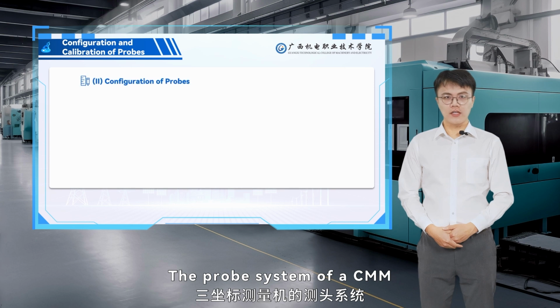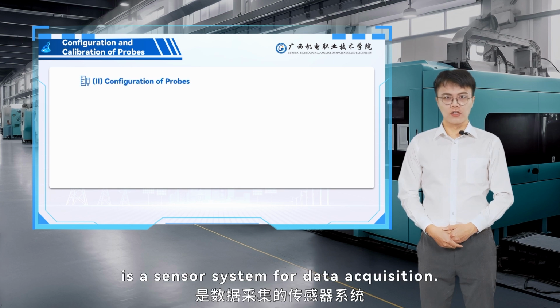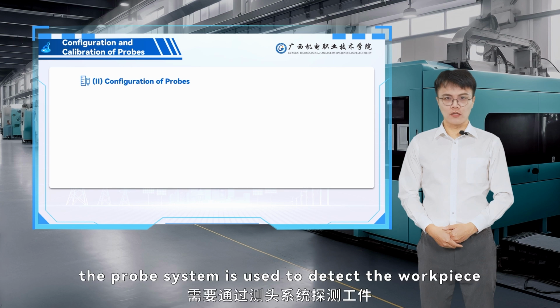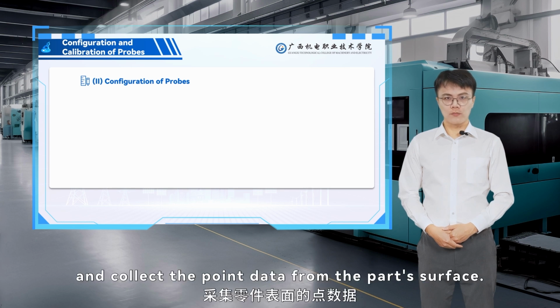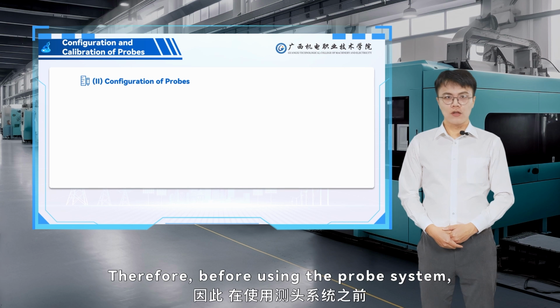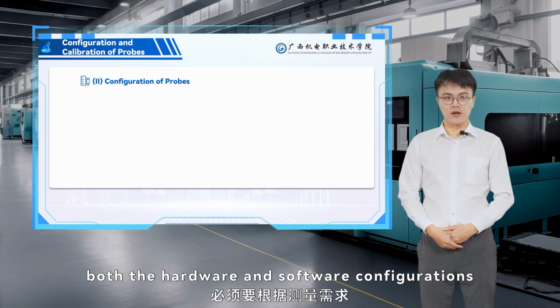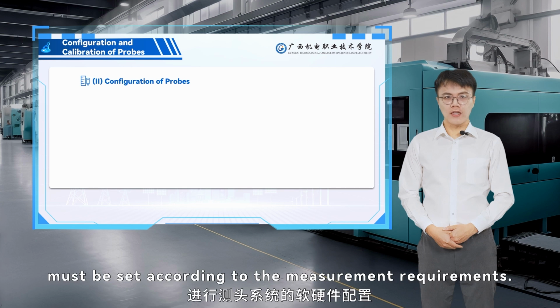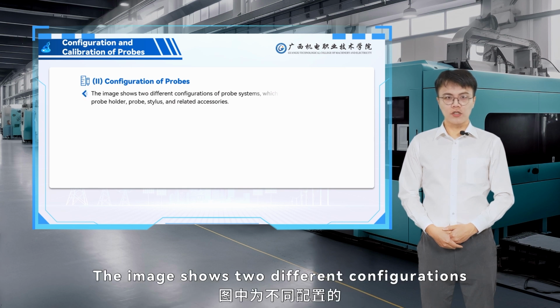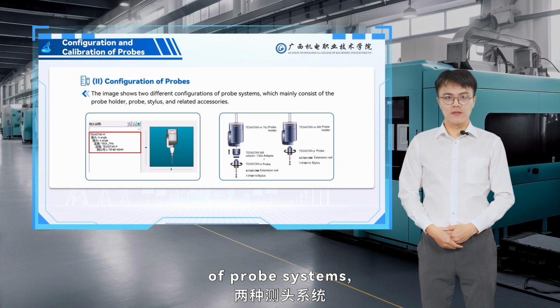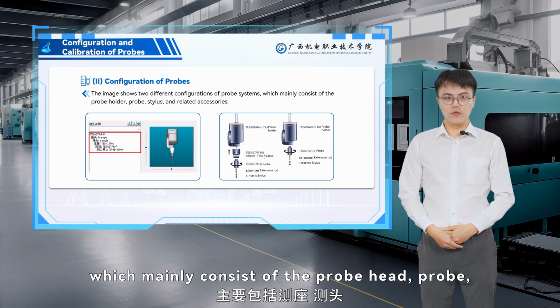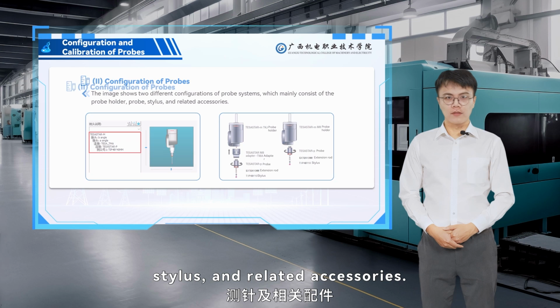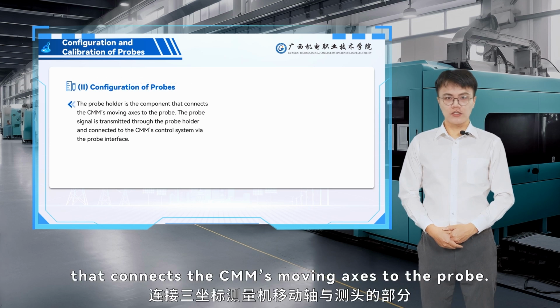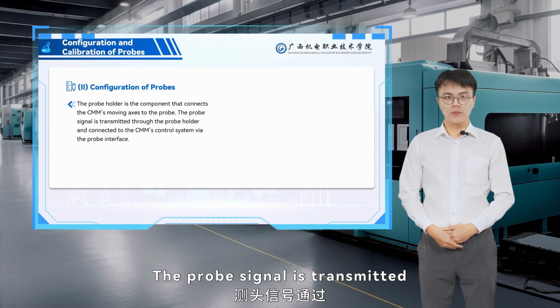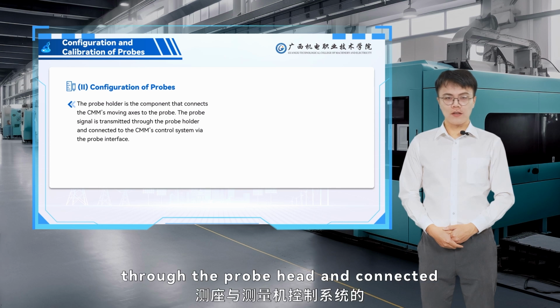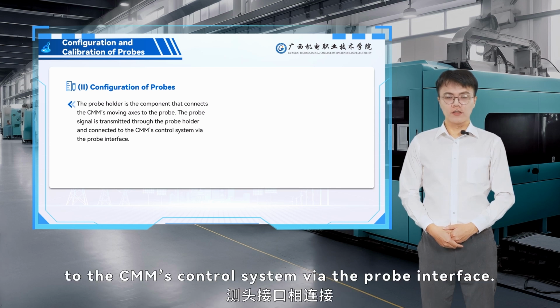The probe system of a CMM is a sensor system for data acquisition. During part measurement, the probe system is used to detect the workpiece and collect the point data from the part surface. Therefore, before using the probe system, both the hardware and software configurations must be set according to the measurement requirements. The image shows two different configurations of probe systems, which mainly consist of the probe head, probe, stylus, and related accessories. The probe head is the component that connects the CMM's moving axis to the probe. The probe signal is transmitted through the probe head and connected to the CMM's control system via the probe interface.